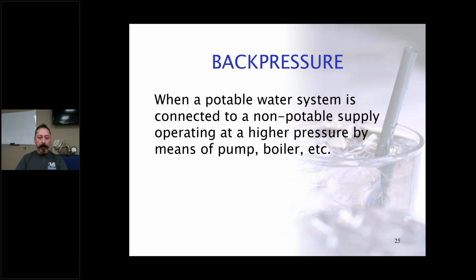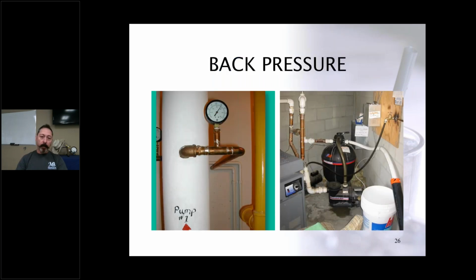And that's when you have two different systems interconnected. So there's a potable system and a non-potable system. If the non-potable system is operating at a higher pressure than the incoming supply pressure from the municipal side or the water purveyor side, that can be forced backwards into the water mains by means of a pump, a boiler, thermal expansion due to heat, or elevation of water too. Inside of buildings, there are lots of different pumps, recirculation pumps, heat pumps and cooling pumps. And if the system supply pressure drops below what the pump is running at, then everything will back pressure into the building or the mains.